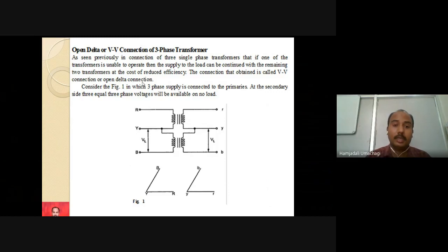So in the previous classes, I told you what is meant by open delta connection. Suppose a three-phase transformer is made by making use of a bank of three single-phase transformers, and it is connected in delta-delta connection. Due to some fault, if any one of the single-phase transformers goes out of service, then at least the other two are ready to serve the purpose. So delta-delta, which was working effectively in the earlier case, if any one of the transformers goes out of service, then that resultant connection we call open delta. Open delta means only two transformers are ready to serve the electrical work.